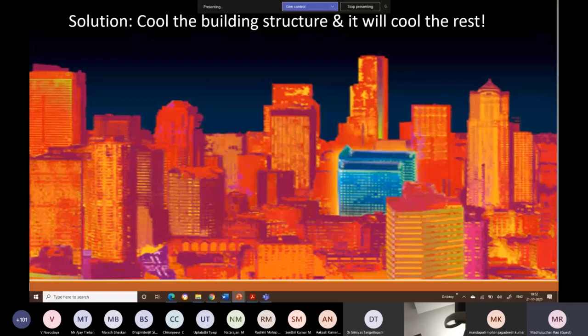How do we do it? This is similar to radiant cooling in terms of the network of pipes and all that, but instead of using a chiller, we use a cooling tower. In this specific case, what we try to do is use a two-stage cooling tower. I'll explain that in a bit.